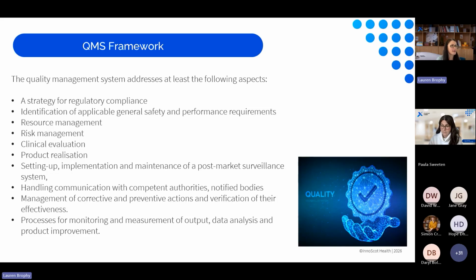Resource management. Obviously, you need to ensure that you have sufficient resource. You need to select and control your suppliers and subcontractors. You need to cover risk management as set out in section 3. You need to have clinical evaluation in accordance with the MDR standards, including your PMCF, which is post-market clinical follow-up. Your product realization, this includes planning, design, development, production, and service provisions within your system.